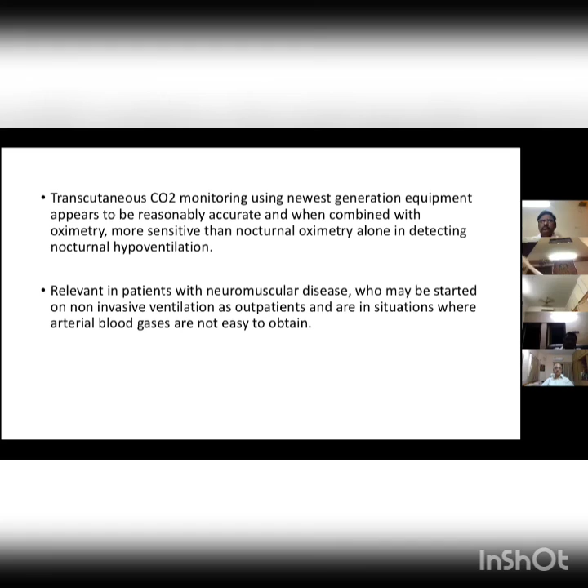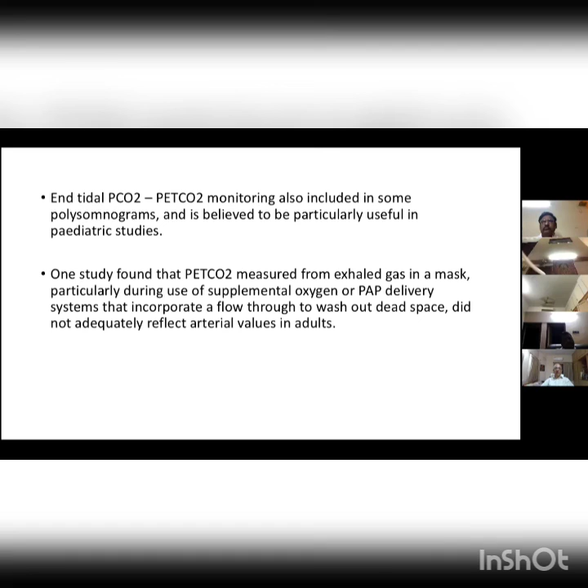End-tidal PCO2, PETCO2, monitoring is also included in some polysomnograms and is believed to be particularly useful in pediatric studies. One study found that PETCO2 measured from exhaled gas in a mask, particularly during the use of supplemental oxygen or positive airway pressure delivery systems that incorporate a flow-through to wash out dead space, did not adequately reflect arterial values in adults. So we should not depend upon a single parameter or single test alone in a difficult situation. Most of the time you will get a reasonable idea.